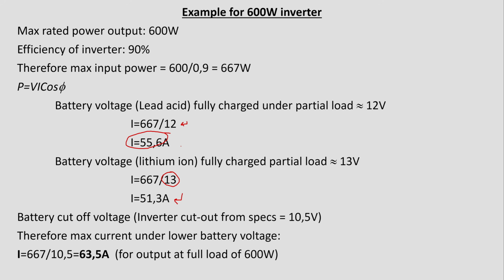So what happens is the wire has a volt drop because it has a resistance. So it's always better to try and use a thicker wire. It will actually allow for a slightly lower current. Remember that the load doesn't change. If you need 150 watts, you need 150 watts. So if the voltage at the inverter is slightly lower, it's going to make it up in current.